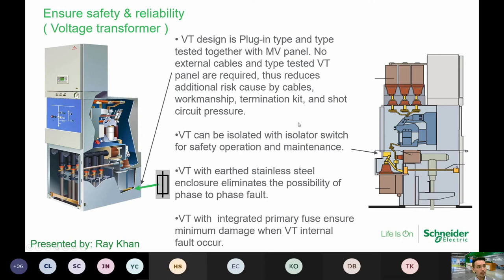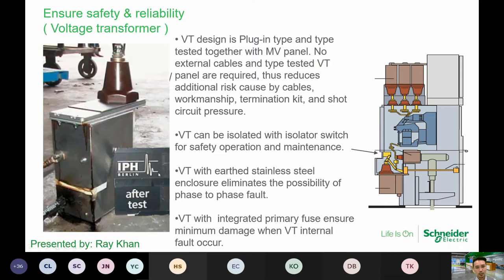Okay, so over in here, it talks about the VTs, so the voltage transformers. The picture on the left, the VT is actually housed in a stainless steel enclosure. So why stainless steel? Because it gives a zero potential, which is safe to touch. And the VT is a plug-in type. Importantly of all, this VT is type tested together with the panel, with the switchgear, with no external cables.